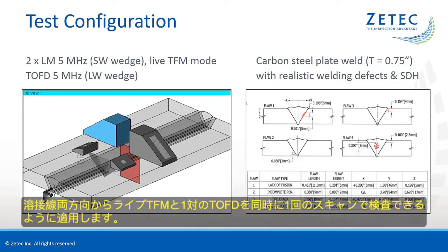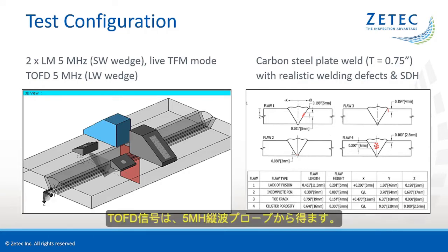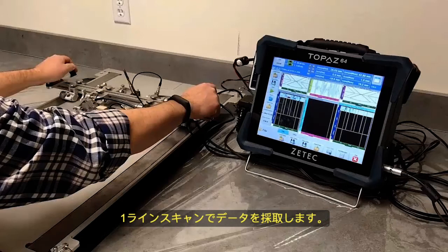The inspection is performed with live TFM from both sides of the weld and a TOFD pair in a single scanning sequence. The live TFM frames are generated from two 5 MHz 64-element linear arrays on shear wave wedges. The TOFD signals are generated by 5 MHz conventional UT probes on L wave wedges. The Zetec weld crawler is used to carry all the probes for a one-line scanning sequence.